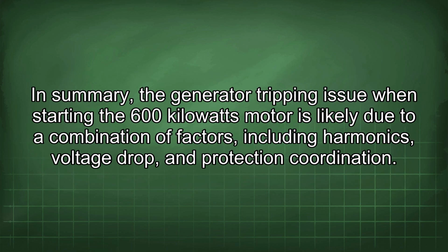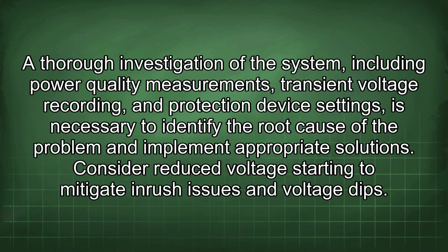In summary, the generator tripping issue when starting the 600 kilowatts motor is likely due to a combination of factors, including harmonics, voltage drop, and protection coordination. A thorough investigation of the system, including power quality measurements, transient voltage recording, and protection device settings, is necessary to identify the root cause of the problem and implement appropriate solutions.